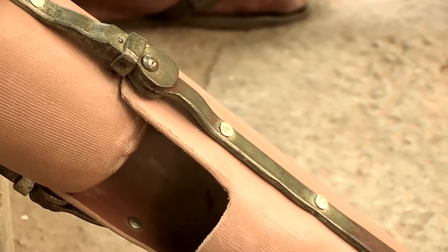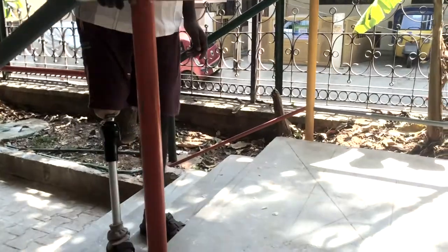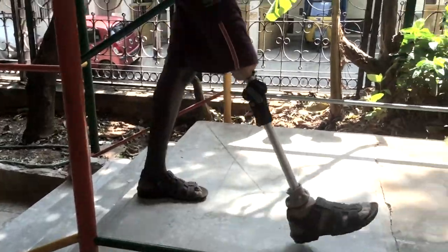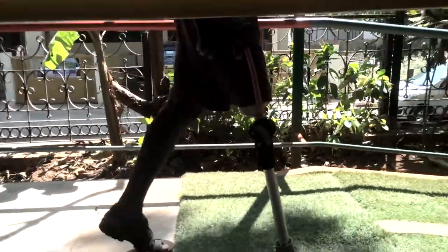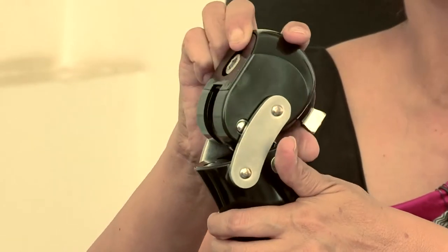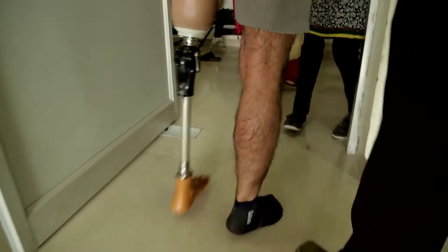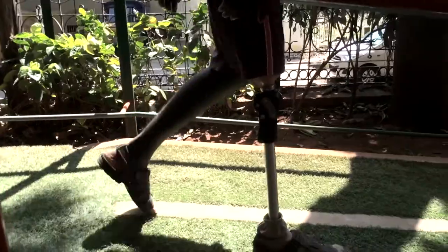So how does the innovative Remotion Knee achieve such natural bending? The Remotion Knee is a polycentric knee — as the name implies, it has a changing axis of rotation as the patient bends his knee. The axis moves throughout the motion.